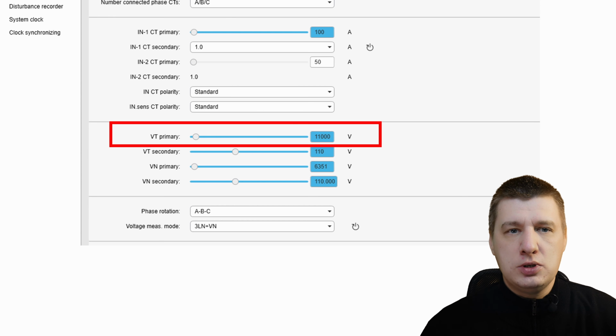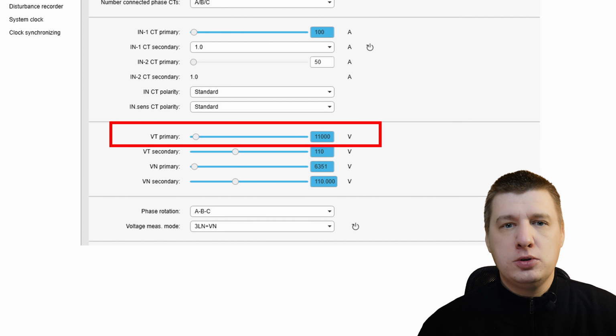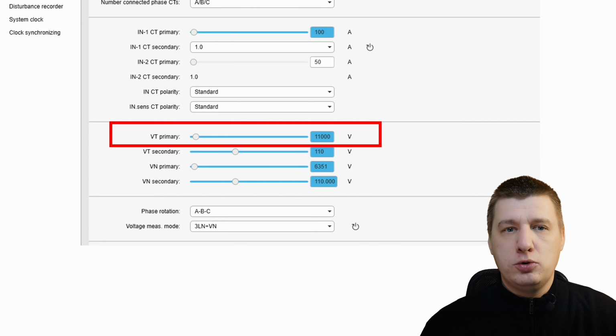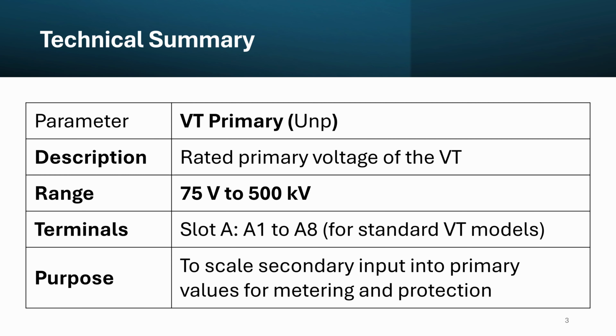If your system uses line to neutral measurements, the relay will handle this math, but it is always based on the line to line voltage you entered for its scaling. Never energize the primary circuits until your VT and CT scaling are verified. If the relay thinks 11,000 volts is actually 400 volts because of a typo, your under voltage and over voltage protection will not work, putting your equipment at risk. Think of VT primary like the scale on a map. If the relay sees 1 centimeter on the map, it needs the scale, the VT primary, to know the real world distance. If you use the wrong scale, you think you're only a few steps away from your actual goal.